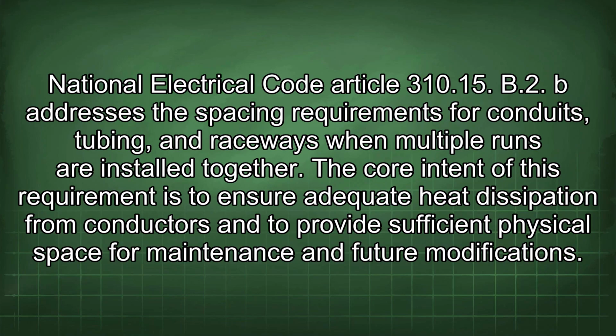National Electrical Code Article 310.15.B.2.b addresses the spacing requirements for conduits, tubing, and raceways when multiple runs are installed together. The core intent of this requirement is to ensure adequate heat dissipation from conductors and to provide sufficient physical space for maintenance and future modifications.